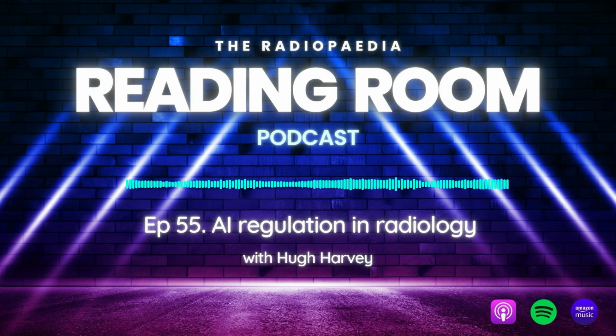So what about post-market surveillance and follow-up? This should always be aligned with the regulation. Companies need to have a data collection plan for how they're going to surveil not just the performance of the device, but technical issues, bugs, feedback, and adverse events, not just for their device, but devices of a similar nature. So for instance, if you have an FDA cleared device under a single product code, you should really be surveilling all other devices under that product code for other technical issues and bugs, because they could affect your system and you might not be aware of them.